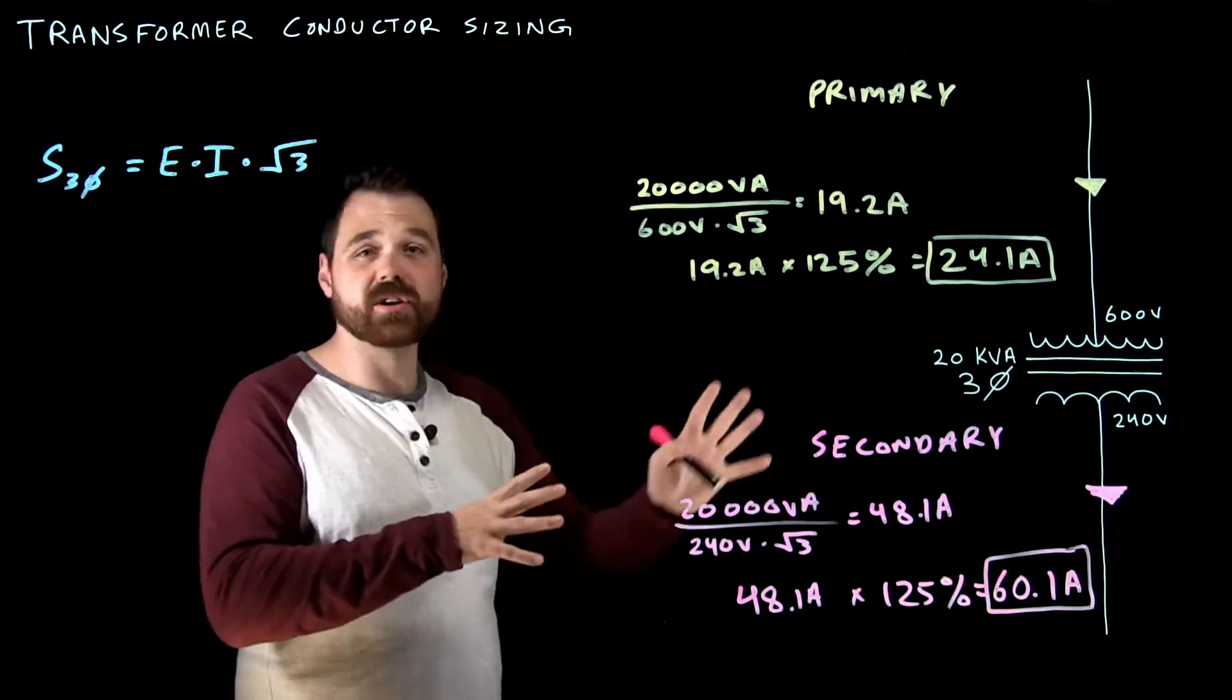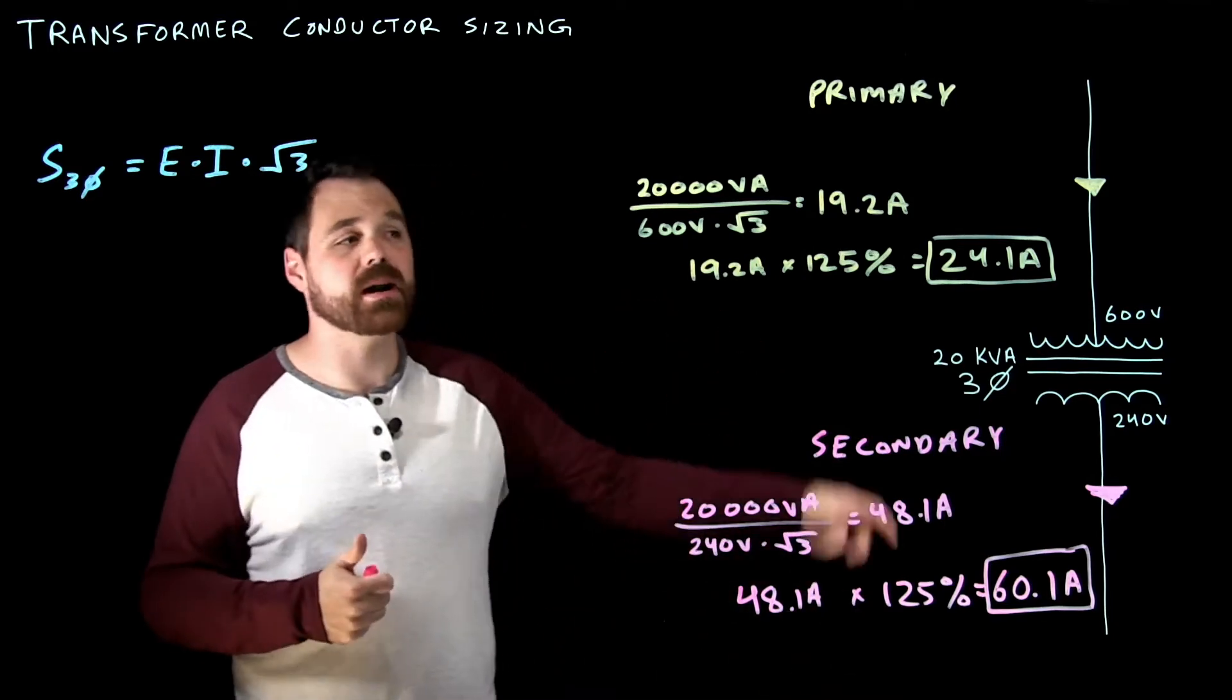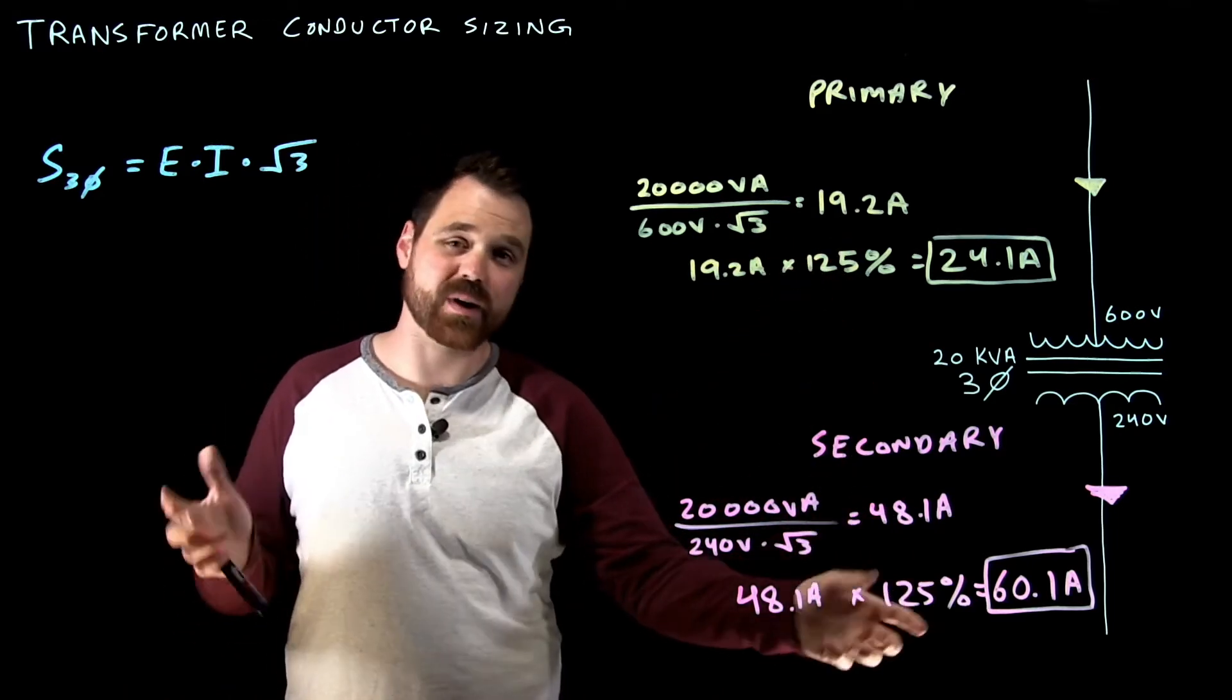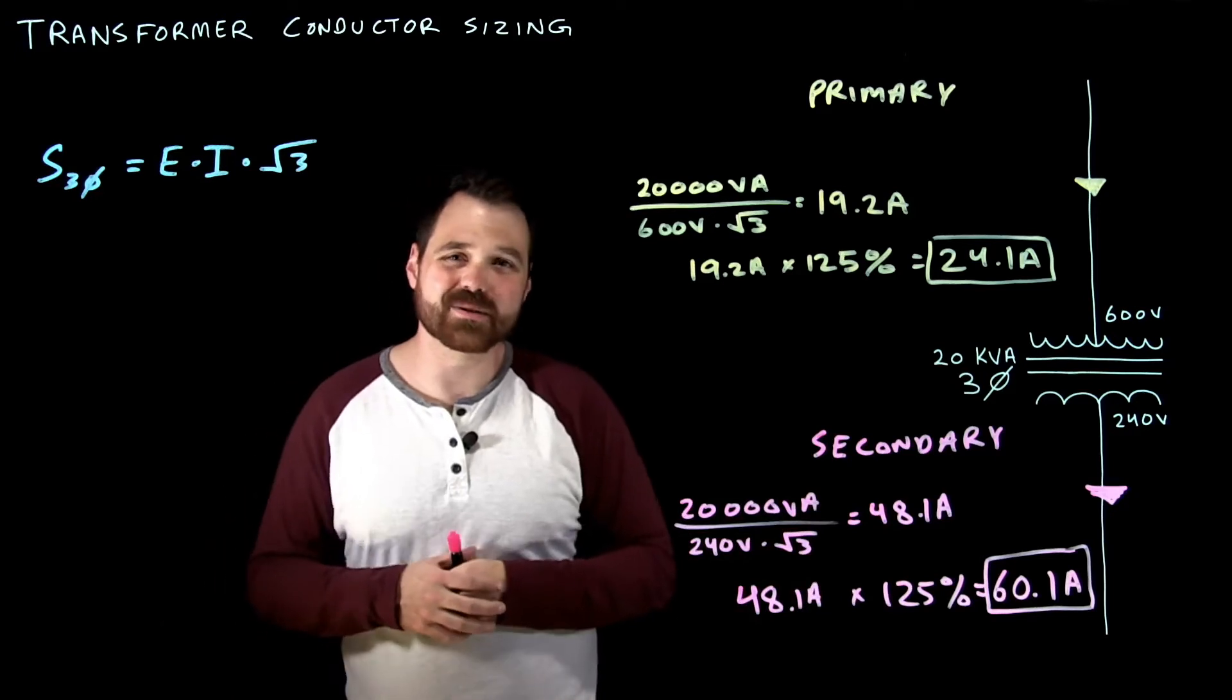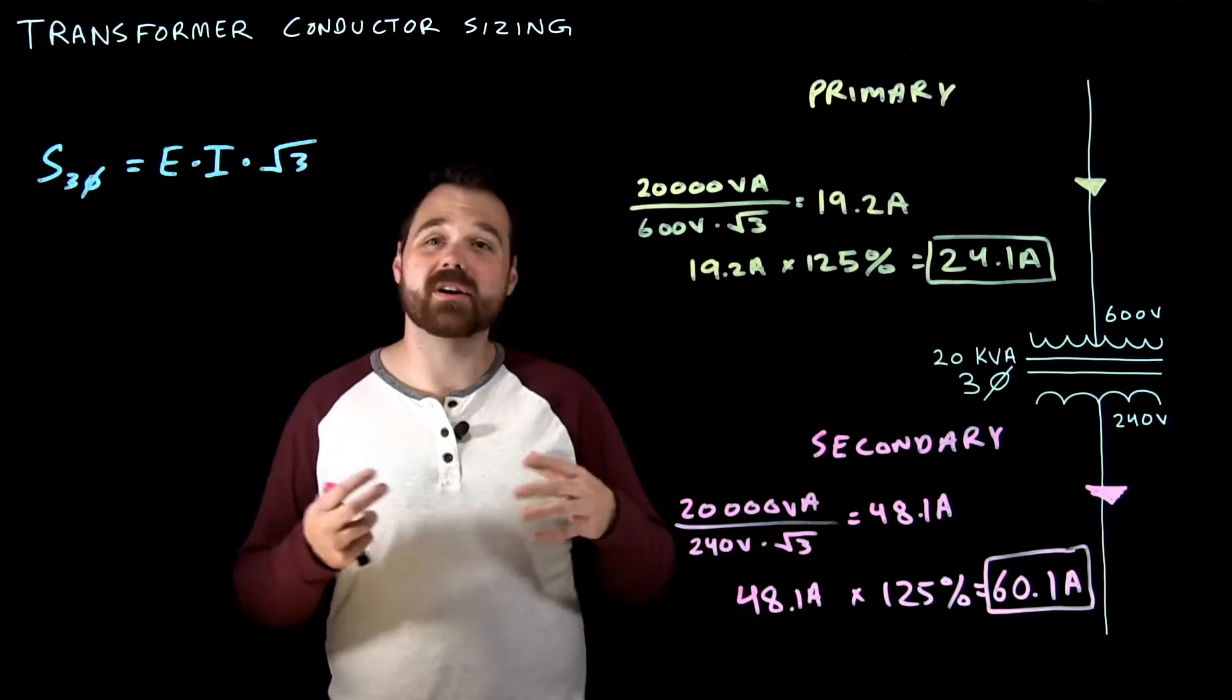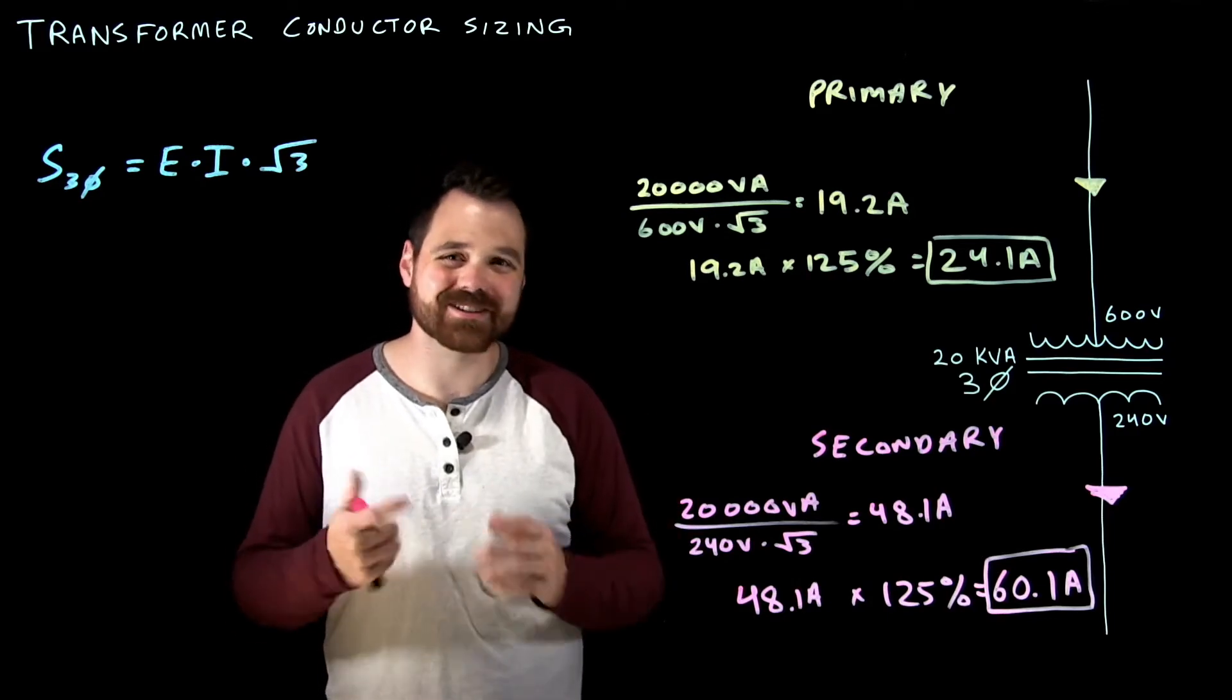So that's talking about a single transformer, very straightforward. 125% for the primary, 125% for the rated current of the secondary. And that's how we would size those conductors. Just one second here, we are going to calculate a transformer bank stick around.